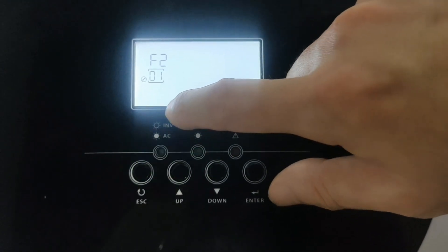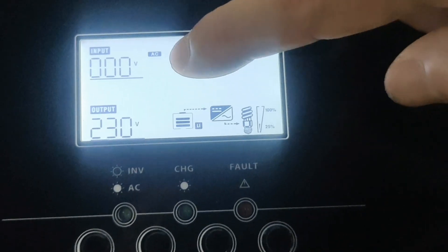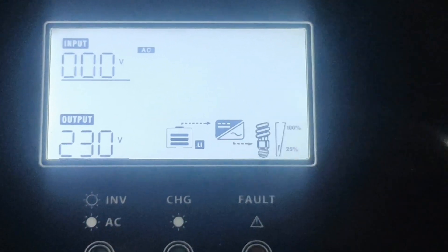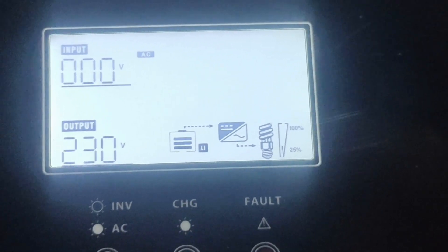Set it to LI in item 01, then confirm to save and exit. Now we look at the screen and the 46 alarm error has been eliminated. There is an LI indicator next to the battery, which means the battery and the inverter have communicated successfully. Note that different inverters have different BMS communication settings.